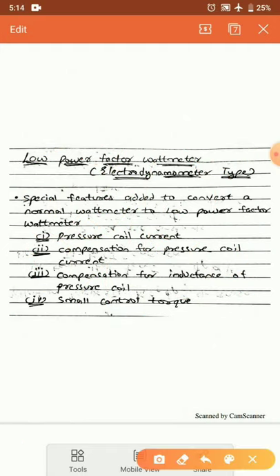For example, let Ip = 10 and Ib = 100. When cos φ = 1, the torque produced would be 1000. But when cos φ = 0.1, that torque reduces to 100 — the deflecting torque has reduced by almost 10 times. This is the first factor due to which a normal wattmeter cannot measure proper power when the power factor is very low.